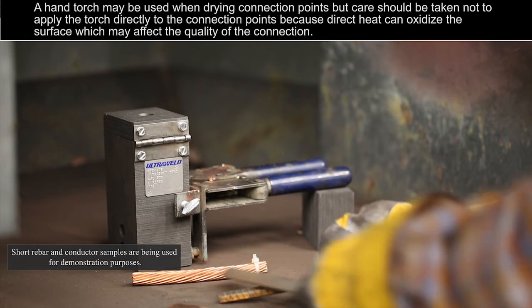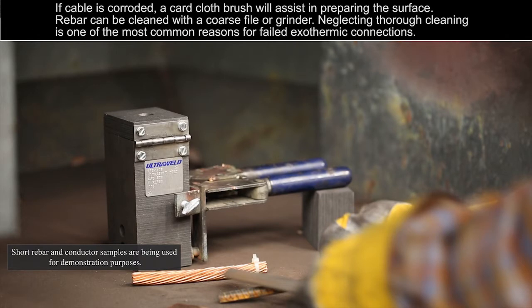A hand torch may be used when drying connection points, but care should be taken not to apply the torch directly to the connection points, because direct heat can oxidize the surface, which may affect the quality of the connection.